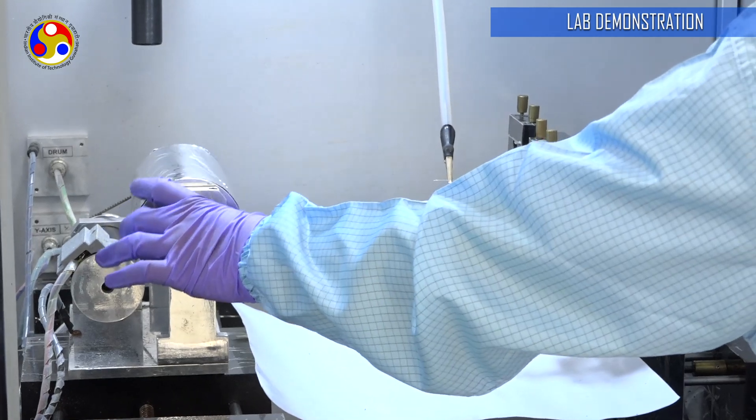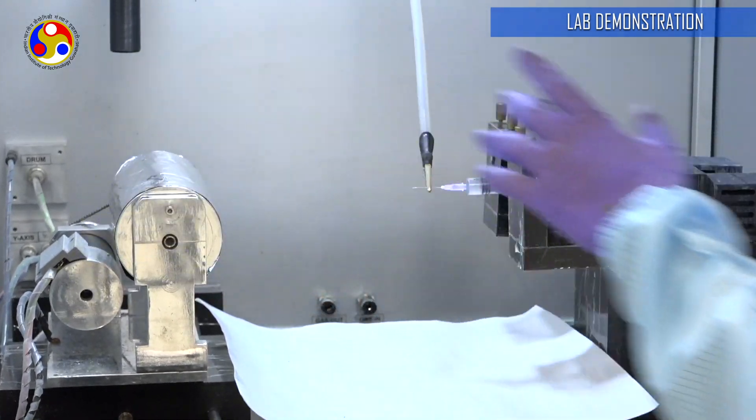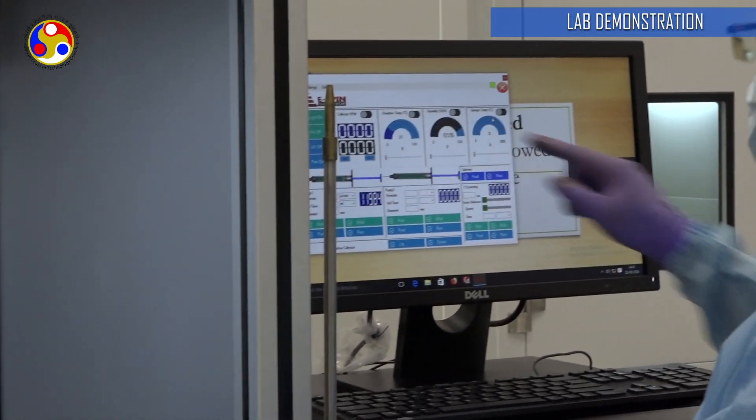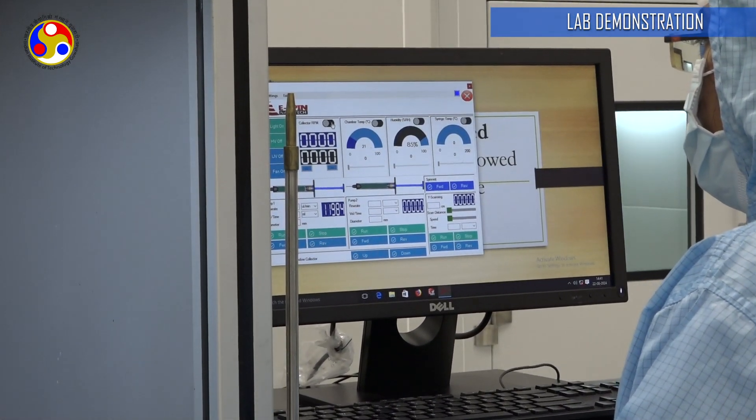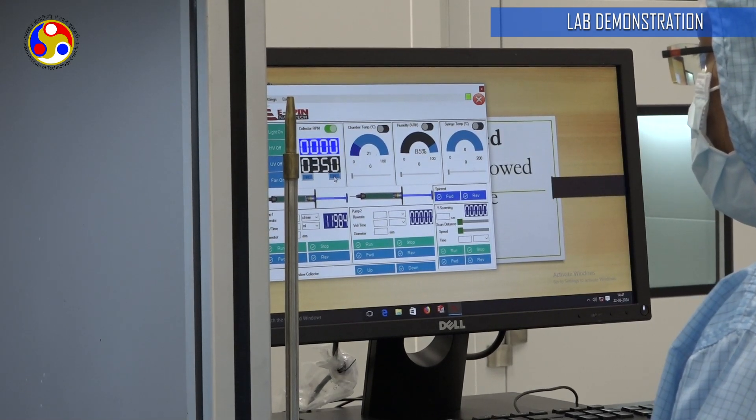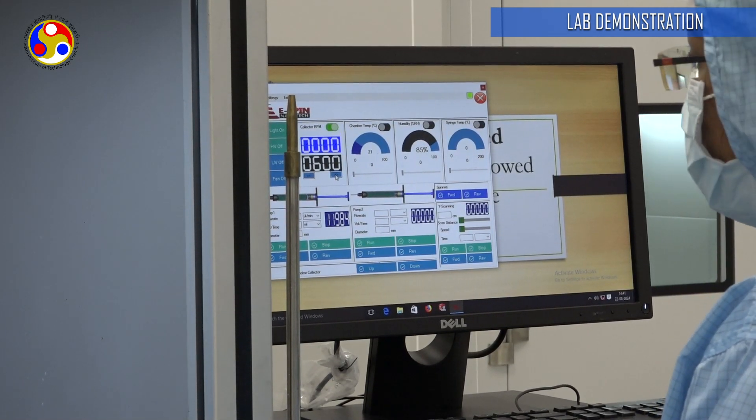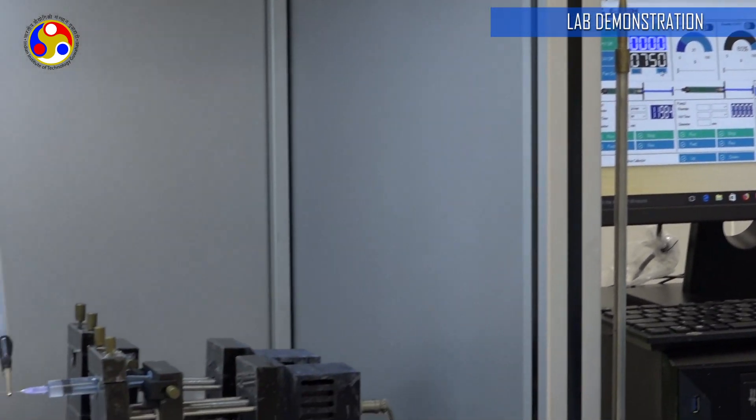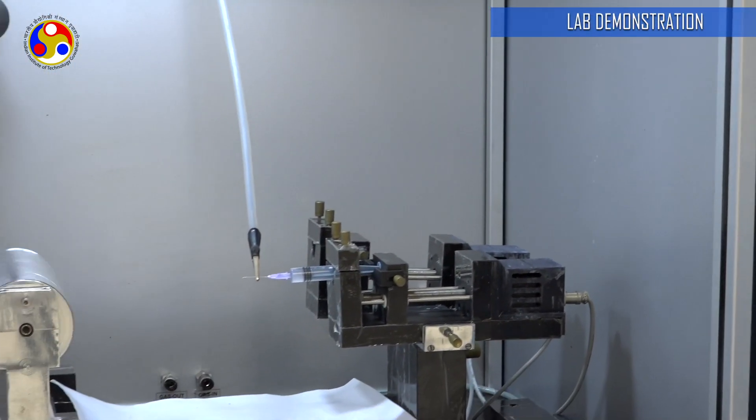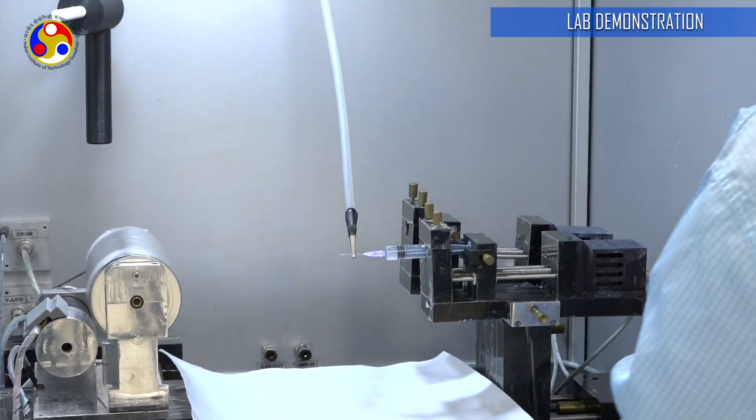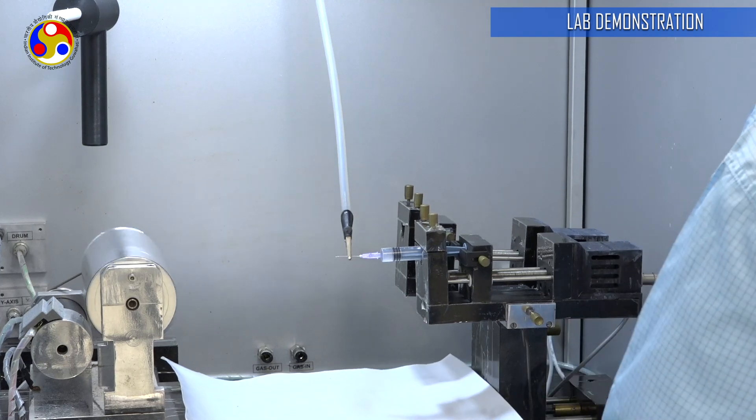The rotating speed of the drum collector can be adjusted through the software interface. Here you can see collector RPM. I am going to just press it on and I am going to give it a value of let's say 700 or 750 like that, 800. It all depends on your requirements.